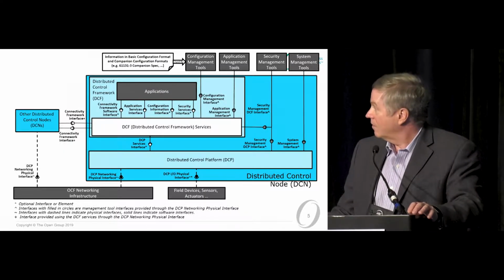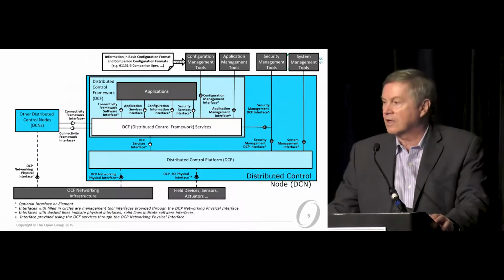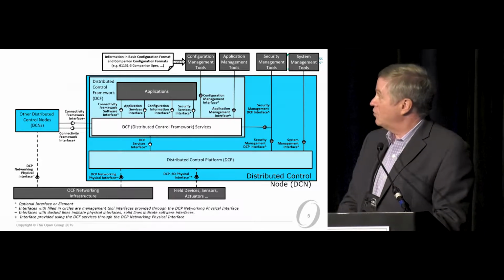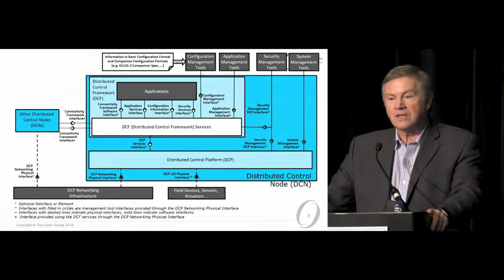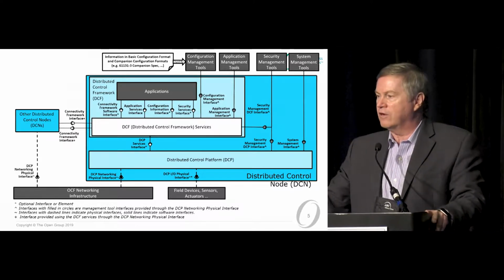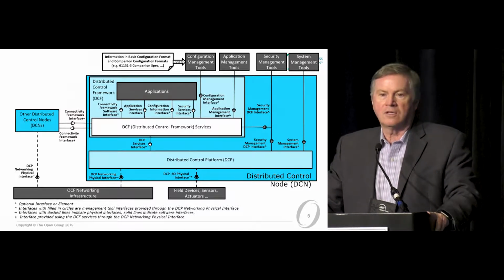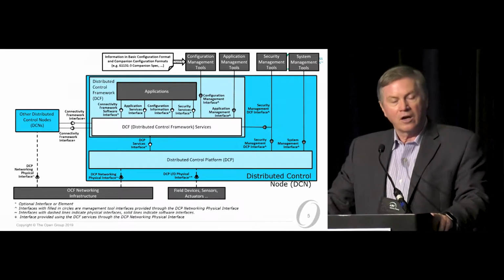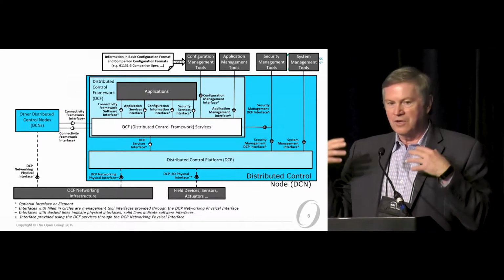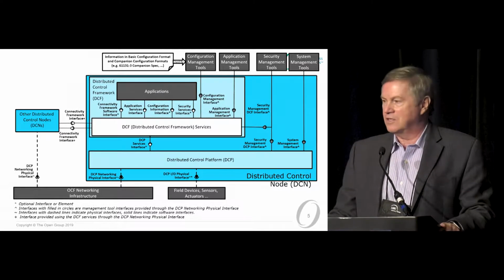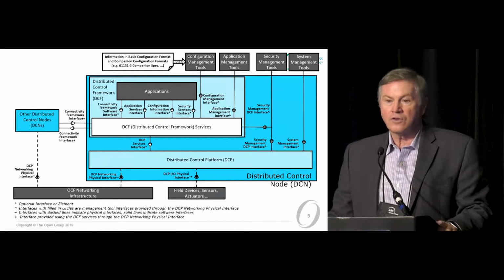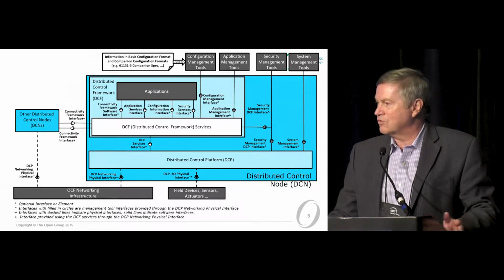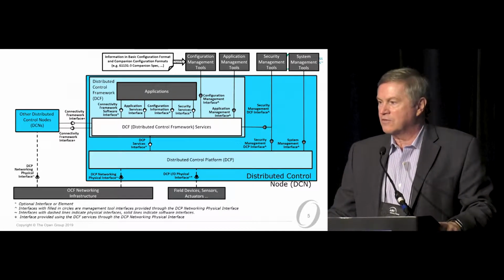This is a little more difficult to read, but there's a copy of it in the technical architecture, part one, and it lays out where we see the future. We see the future as basic configuration information, so that I can configure an entire system independent of where these things are actually going to operate. That means I've defined the I/O and the structure, whether it's organized by units, production lines, or process cells. I can also configure the control strategies associated with that, whether they are IEC 1131 or 61499.